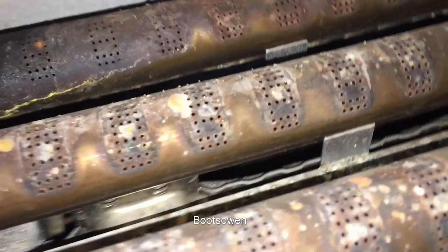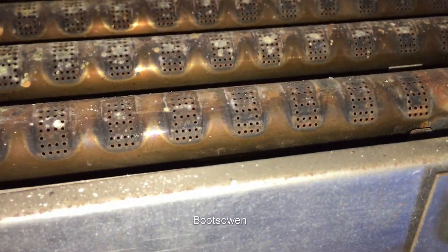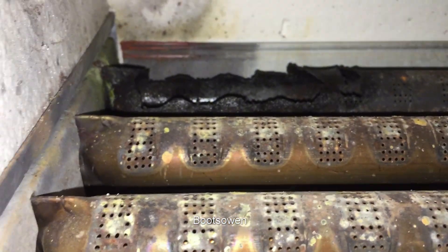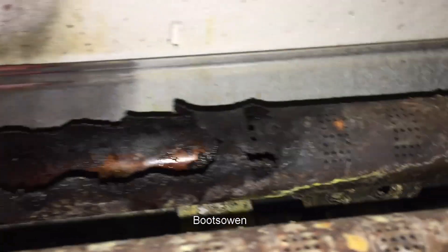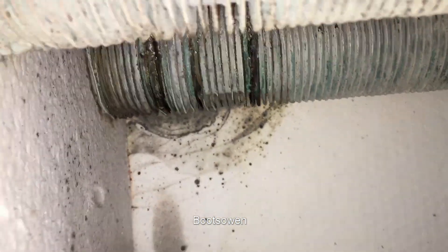The gas goes into this four tube array from below, mixes with air, and comes up. These tubes are only made of some kind of galvanized tin or something. The water has been dripping onto that, making it worse — it's probably getting more flames, causing more heat in that corner.